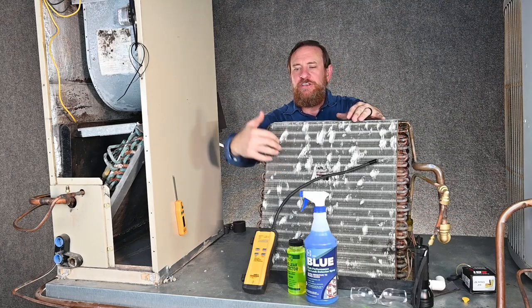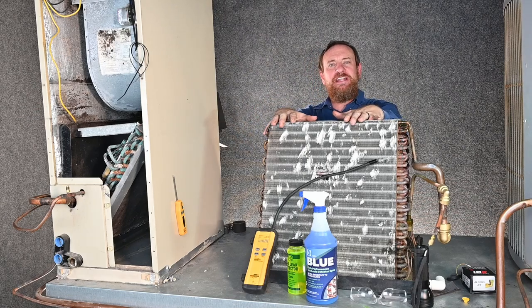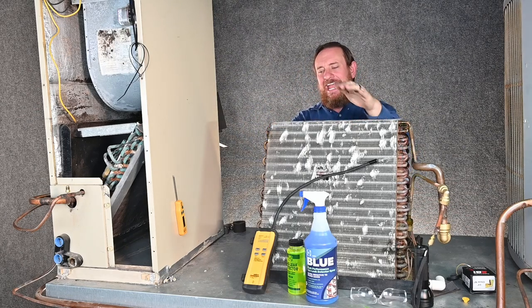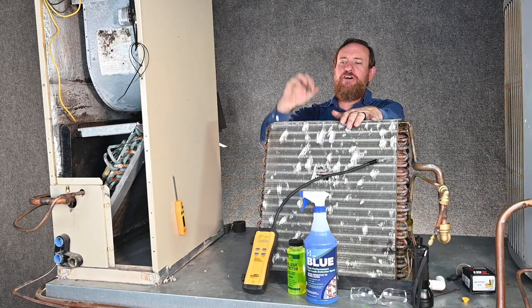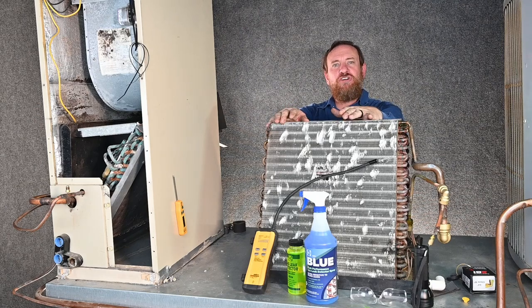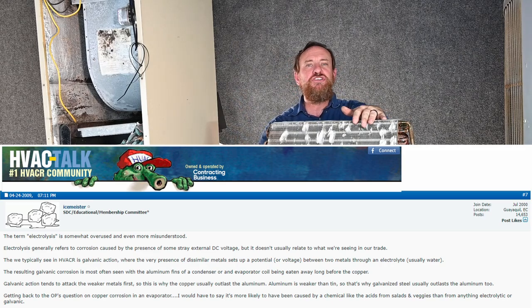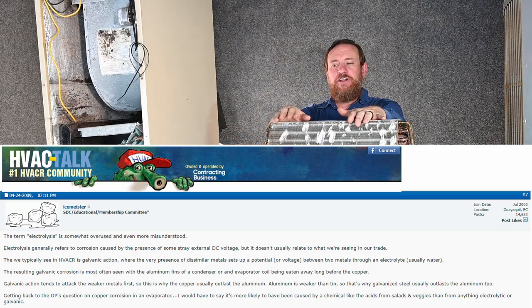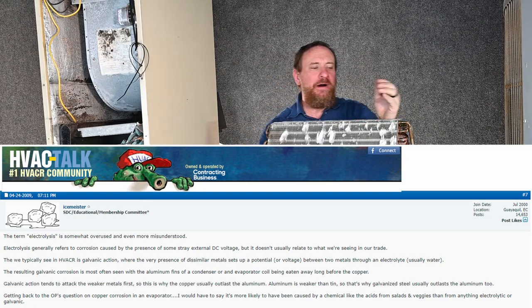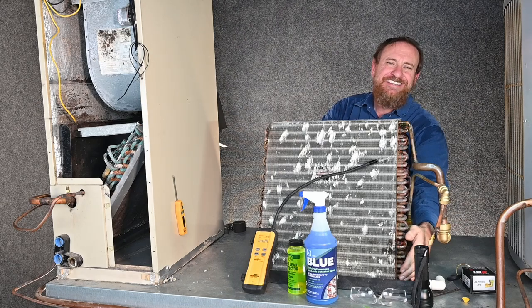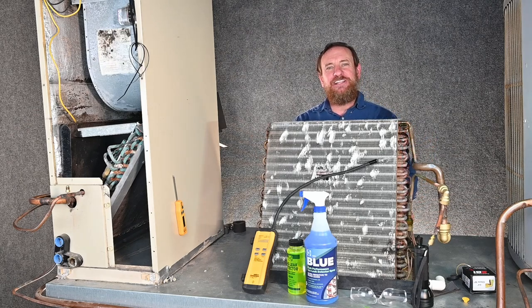We also have to consider electrolysis. We have aluminum fins, copper tubing, and galvanized metal on the end plates — multiple dissimilar metals in one environment — plus airflow, moisture from condensation, and vibration. When two dissimilar metals are together with electrons moving through them, it causes corrosion. That's why you'll often see leaks at the very bottom of the coil or where the distribution tubes enter, because those spots are the wettest.